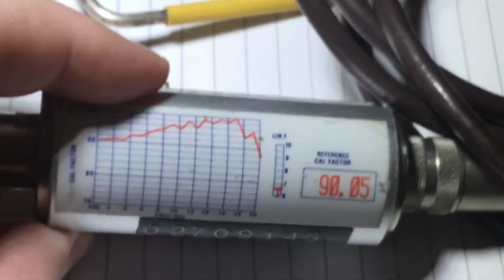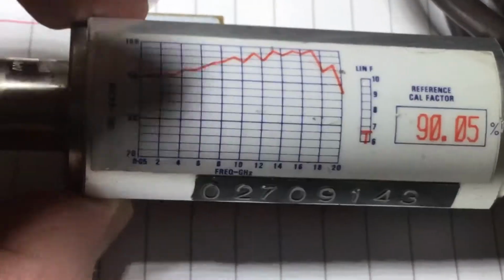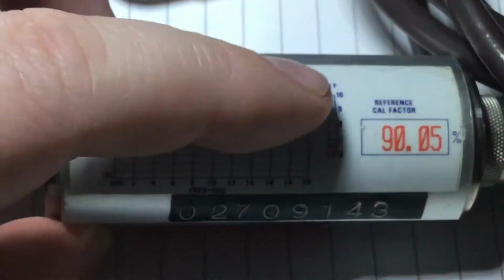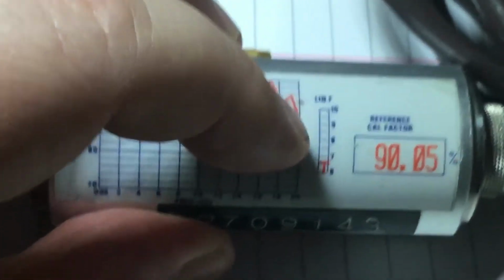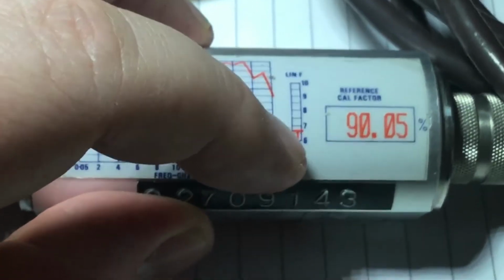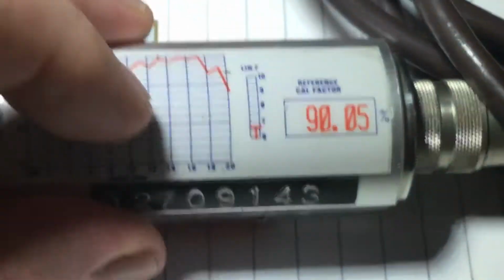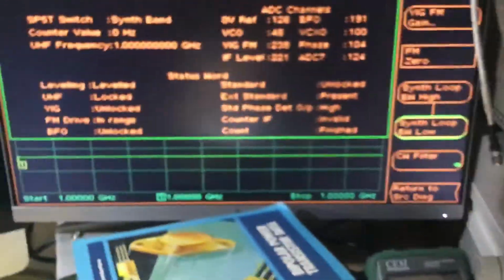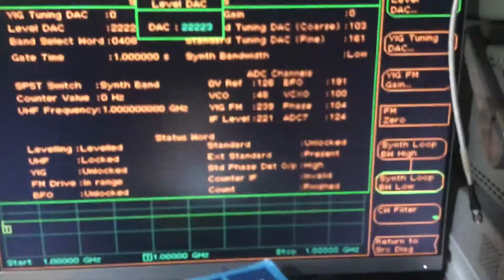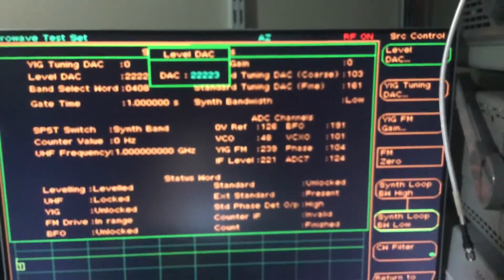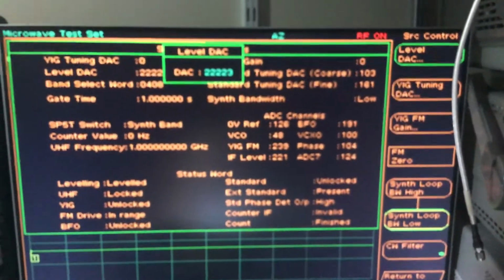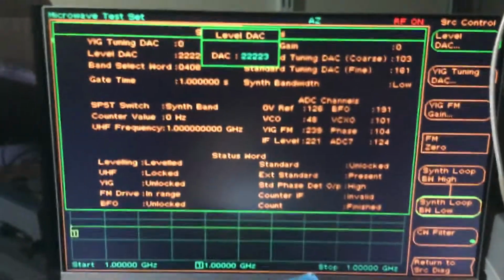a proper table of levels as opposed to a graph. And then we've got the linearity factor which has to be entered in, and then we've got the cal factor. So we enter all these 3 pieces of data into the Marconi test set when we're actually dealing with the power measurement. Now as well as that, there's lots of other diagnostics menus on there as well, so it's quite interesting what you can do with it.